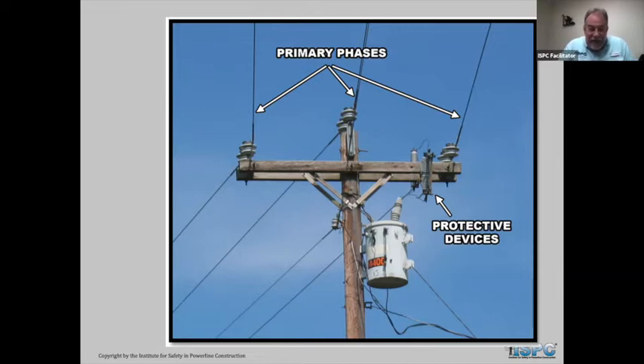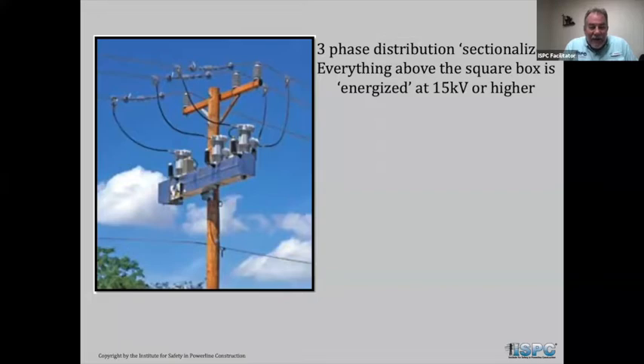So the secondary coming out of the transformer, the neutral in the secondary is also bonded to that system neutral. So the current returning back to the transformer from the customer is also carried through that transformer and bonded onto that system neutral. So usually about this time, I'll start getting a lot of questions from my class as to how come we haven't been electrocuted in the past.